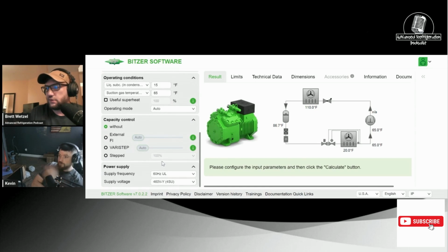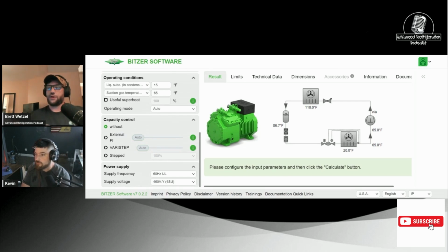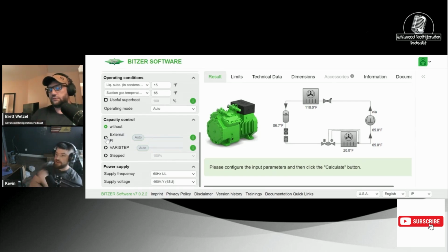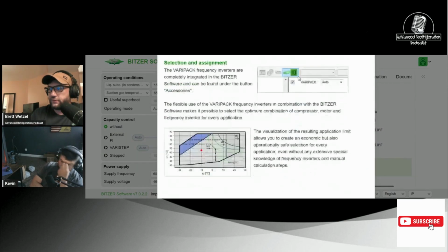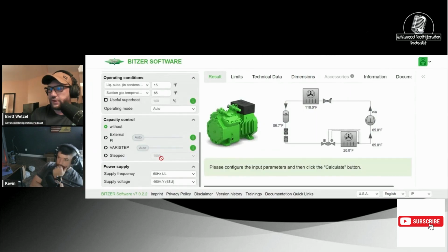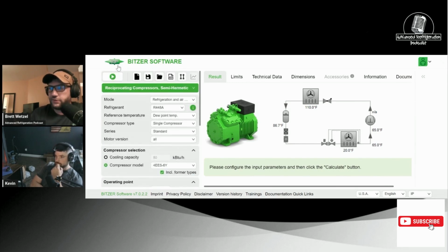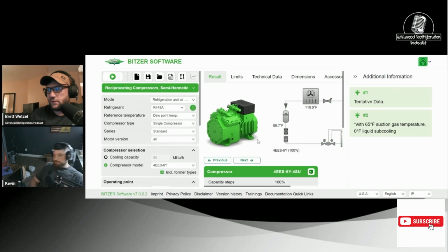Oh, and then down here you can also change it to with external or without control. So you could actually check it at different hertz of what it should have. That would be the Bitzer digital compressor function. External drive, you can hit the little thing right here. Frequency drives. Look at that, it gives you a little bit of explainer. Then you also have stepped, if you have unloaders on certain sections. We're doing 60 hertz, and we're doing 460 volts. Yeah, that's fine. Now what we're going to do is hit the play button, the calculate button. Yay, it worked.